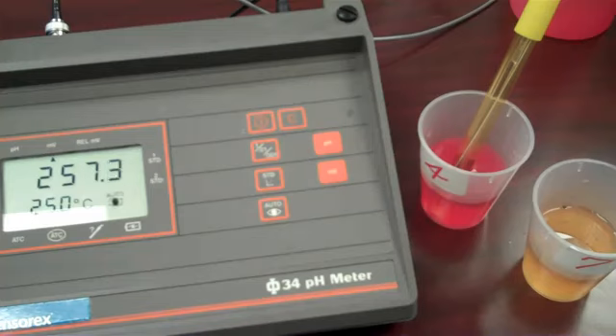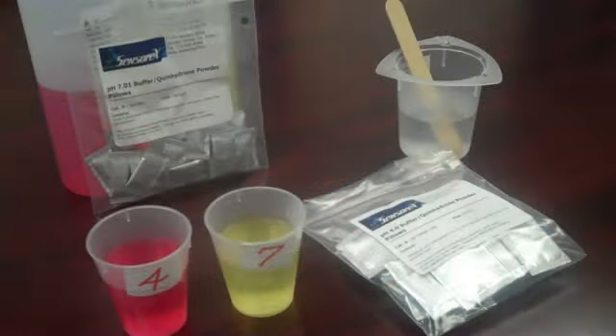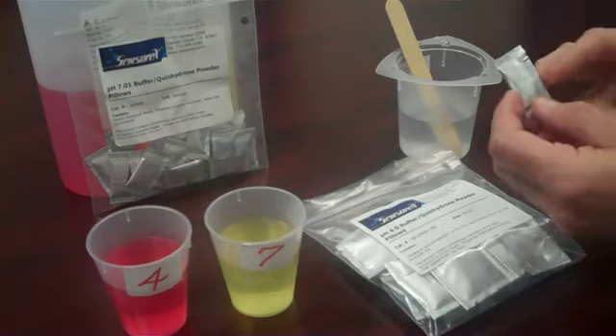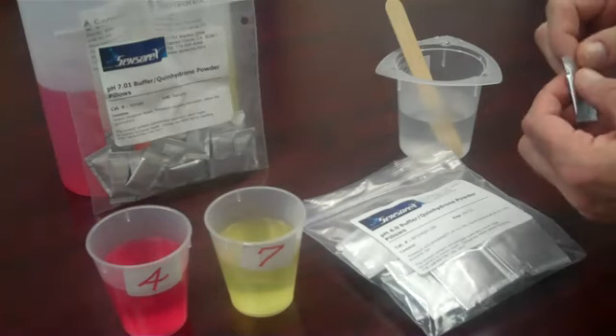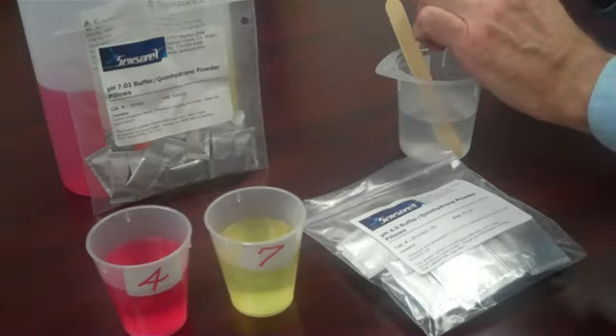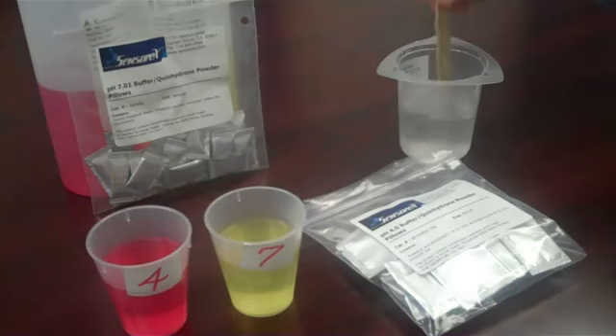The two-point verification step will ensure that the ORP sensor is still working properly and meet the requirements of those ORP controllers that require 2-point inputs for standardization. Sensorex also offers convenient foil sachets that provide the same 2 points for ORP calibration. The contents of a single sachet packet is opened and added to 100 milliliters of clean water, stirring briskly for a few seconds to dissolve it.